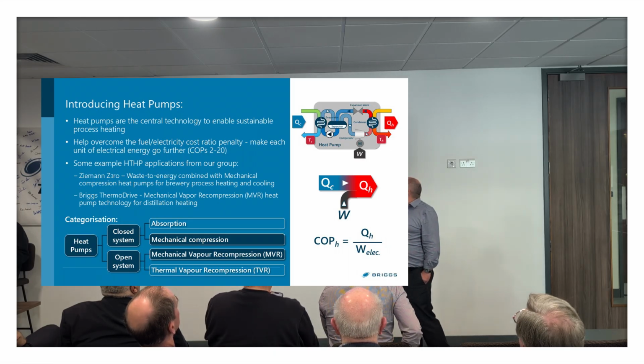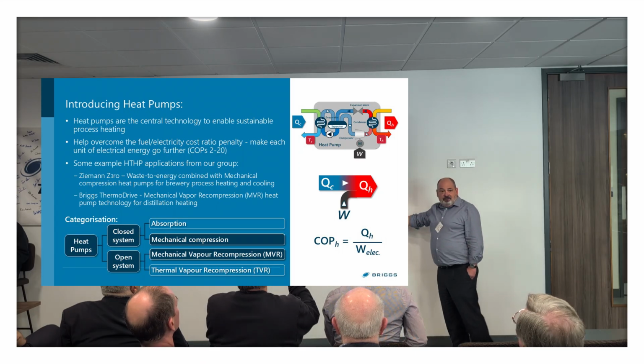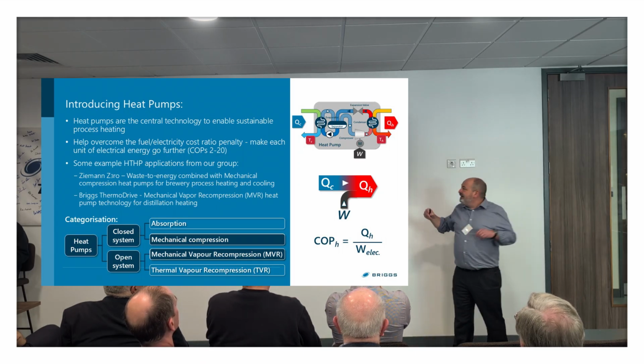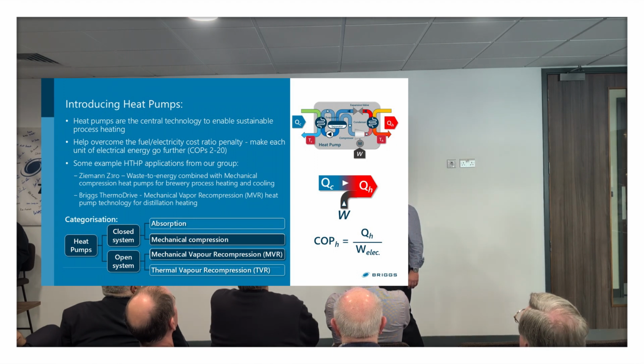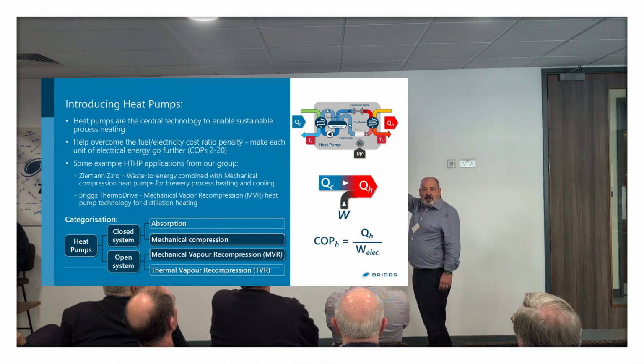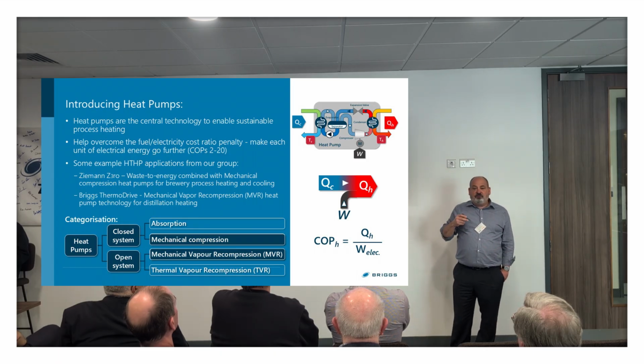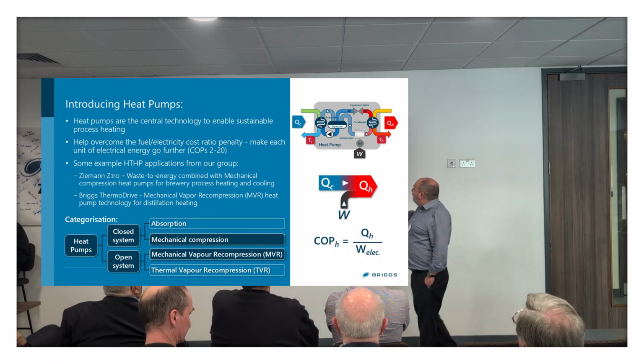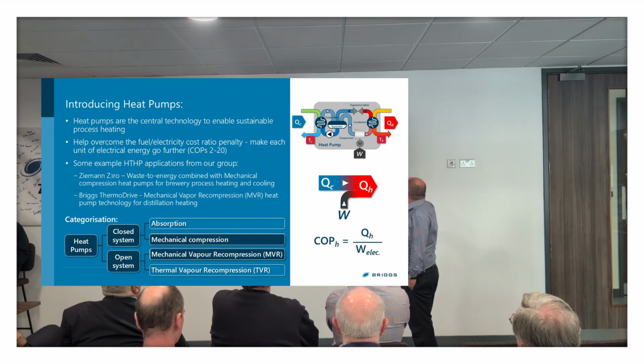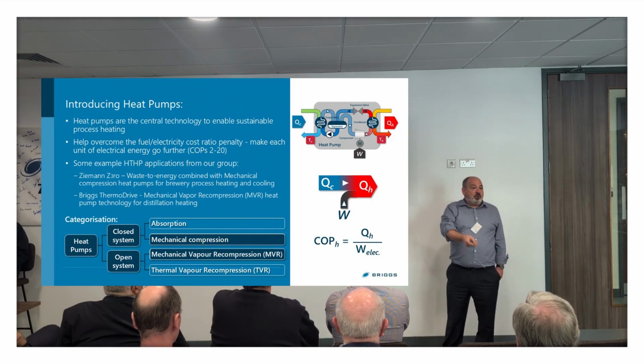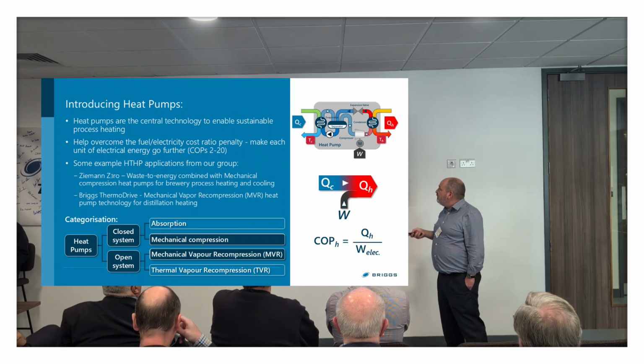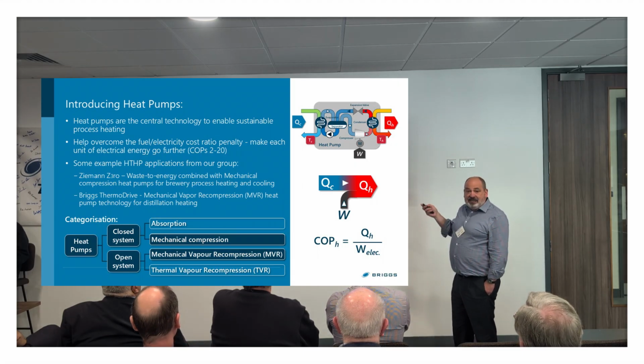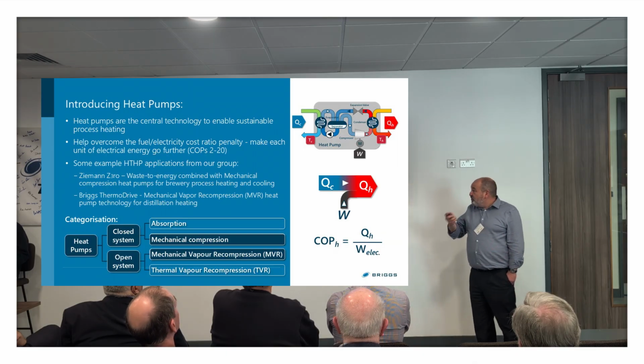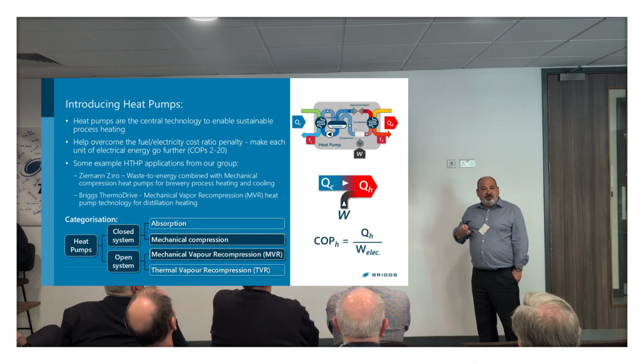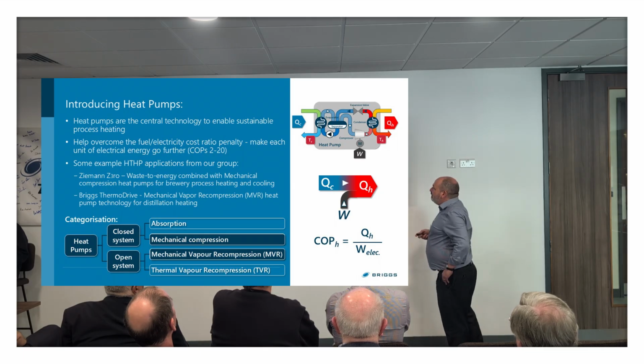And typically for a heat pump, it can be between 2 and 20. That's a very big range. But even at the lower scale, what 2 means is 1 unit of electricity gives you 2 units of heating output. And clearly, a COP of 20 means that 1 unit of electricity gives you 20 units of heating output, which obviously sounds and is much better than a coefficient of performance of 2. But 2 still stretches your kilowatt hour of electricity by a factor of 2.